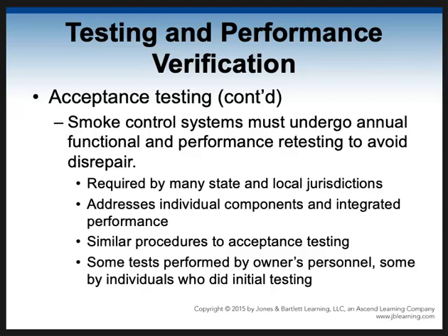Here in the state, Title 19, the State Fire Marshal's Code, has rules in there about the testing of smoke control systems, how often. There's some things that are visual, like we've talked about, and some that they actually run. So these are performed by the owner's personnel, but usually they're going to be witnessed by fire department personnel as well. We don't do the test, we witness the test. Remember that. I've mentioned this a lot in our fire prevention course. Never, ever touch the equipment. It's not your job, and if something breaks, they're going to blame you. You witness it, you visualize it, you document it, and you do all of that.